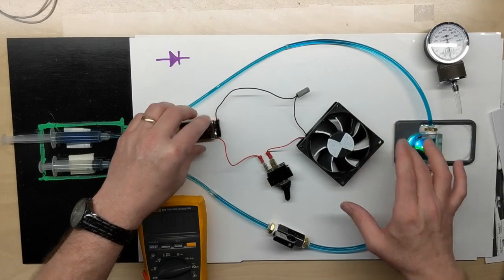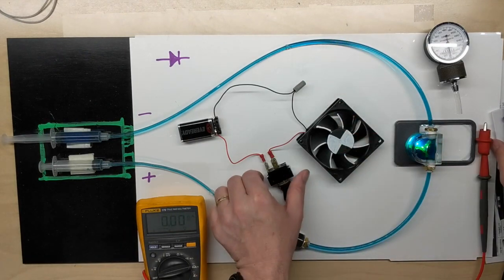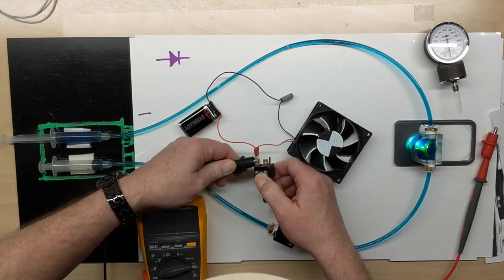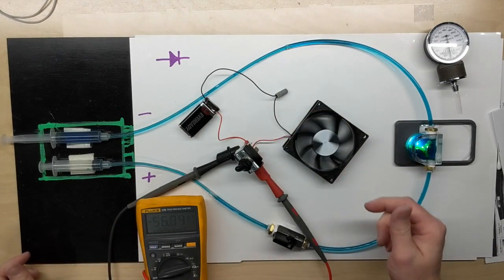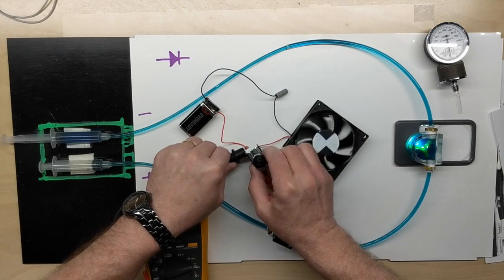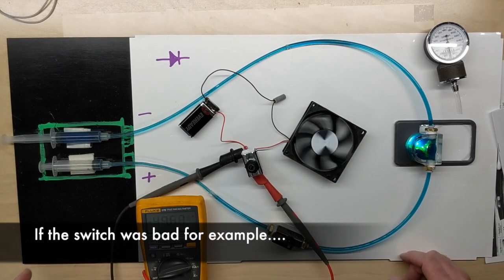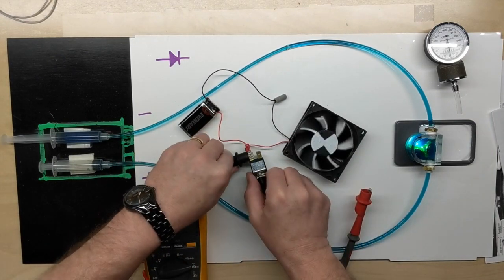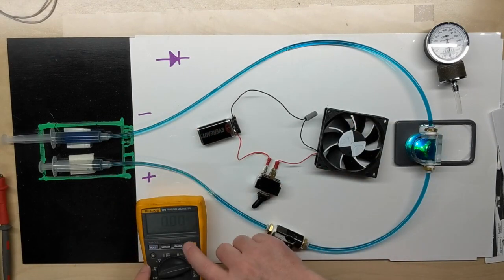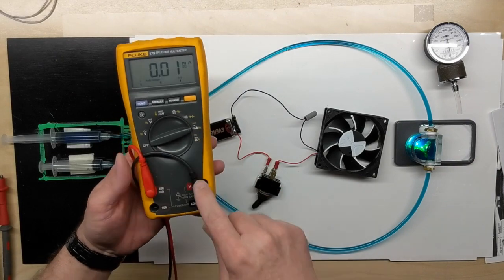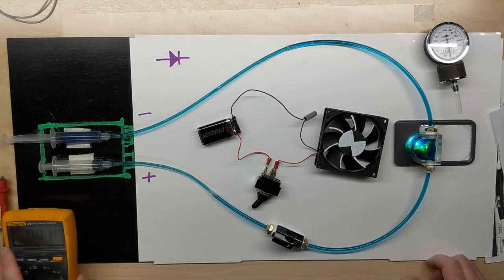So I mentioned there was more than one way we could do that check, just meaning that I didn't have to break the circuit here. If it was a way to test this without breaking the circuit, and this will help in troubleshooting as well, I could have went across my switch, which basically just jumped the switch out using the meter. So there's a contact point there that was open due to the switch being actually turned off. And by jumping it out, I have verified the circuit works. So I took that open circuit and I closed it with my meter, because the current actually goes through the meter as it's being tested. It actually uses a shunt resistor to read off of, which we'll get into in later episodes.